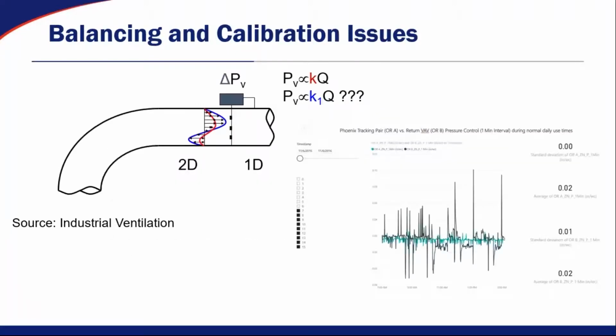Now, when it comes to field balancing, you can see in this example that the red and the blue lines shown there are actually the flow profile of the air going through the ductwork at two different velocities. Looking at that, the way air tends to flow in a system that has an elbow, air wants to travel in a straight line. So the air will go up the elbow, it will actually stick to the outside of the elbow, and that's why you have that inverted S flow profile, where you have a lot higher velocity on the outside of the elbow or the outside of the ductwork, and on the inside of the elbow or the inside of the ductwork, you actually have some reversion or backwards flow.